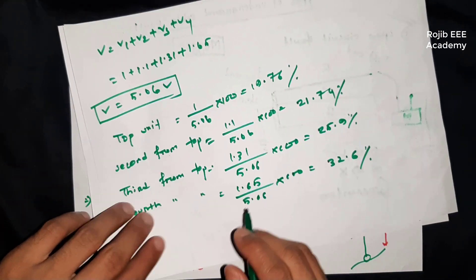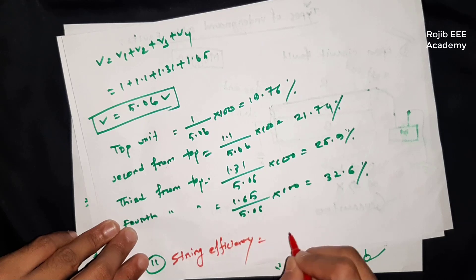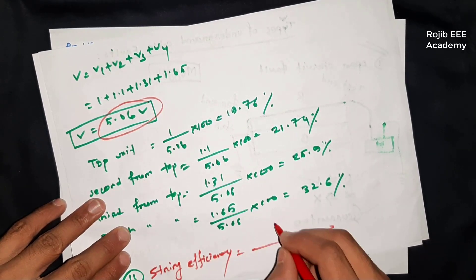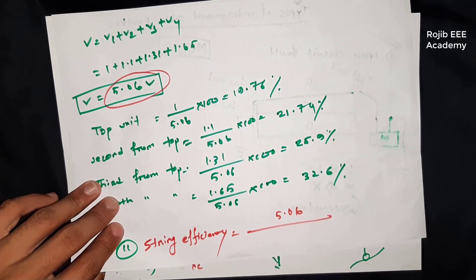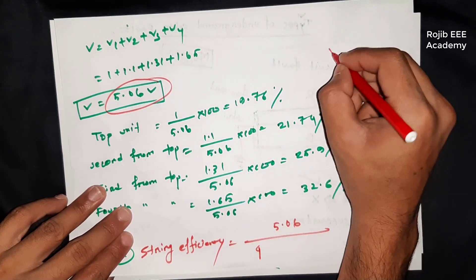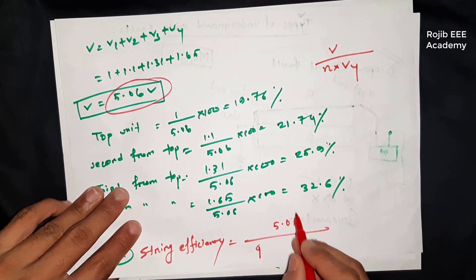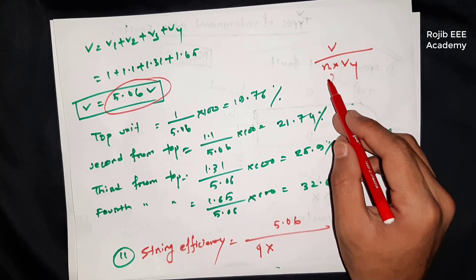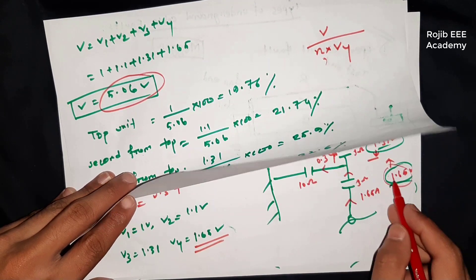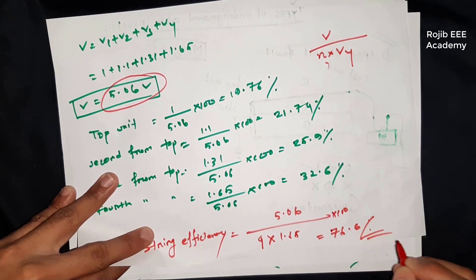Now we calculate string efficiency. The formula for string efficiency is: total voltage across the string divided by N times the voltage across the nearest conductor unit. Total voltage V equals 5.06, N equals 4 (four insulators in the string), and V4 equals 1.65. So string efficiency equals 5.06 divided by (4 into 1.65) into 100, which gives 76.6 percent.